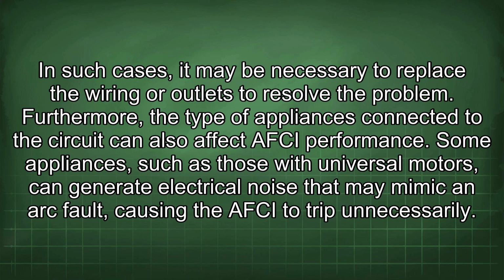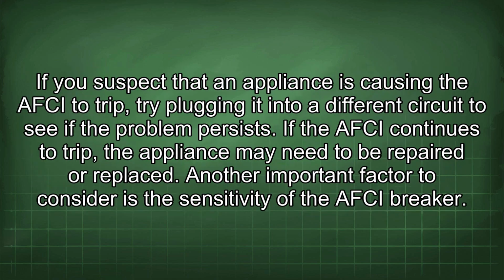Furthermore, the type of appliances connected to the circuit can also affect AFCI performance. Some appliances, such as those with universal motors, can generate electrical noise that may mimic an arc fault, causing the AFCI to trip unnecessarily. If you suspect that an appliance is causing the AFCI to trip, try plugging it into a different circuit to see if the problem persists. If the AFCI continues to trip, the appliance may need to be repaired or replaced.